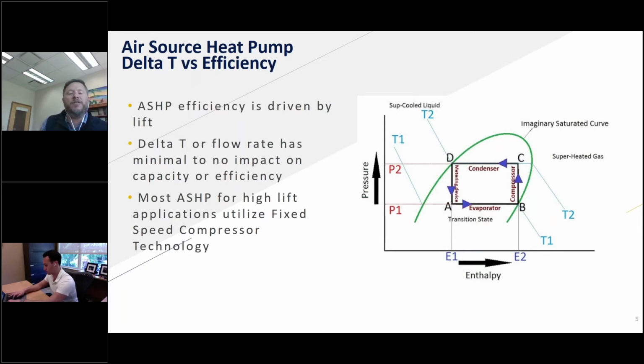So if we look at what air source heat pump efficiency is driven by, what I've got here is the refrigeration cycle. The bottom line between A and B is the evaporator, where we're removing the heat. That's the low side of the system, or the suction side. The condenser, the line between C and D, is where we're rejecting the heat. When we're heating, that's where we're putting the heat back into the hot water to deliver to the building. That's the high side of the system. And the difference between the two is what is known as lift, which is really the work that the compressor has to do.